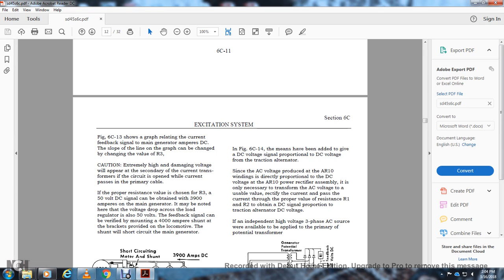The shunt will short the circuit with the main generator. In figure 6C-14, the means that has been added gives the DC voltage signal proportional to the DC voltage from the traction alternator. The AC voltage developed in the AR10 alternator field windings is directly proportional to the DC voltage of the AR10 field power rectifier assembly.